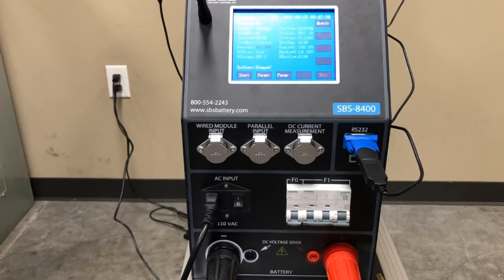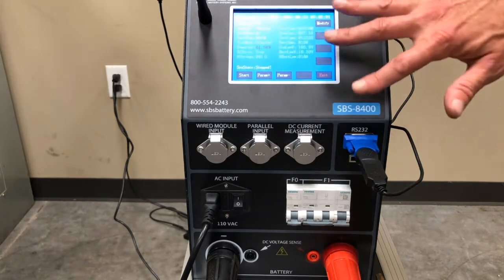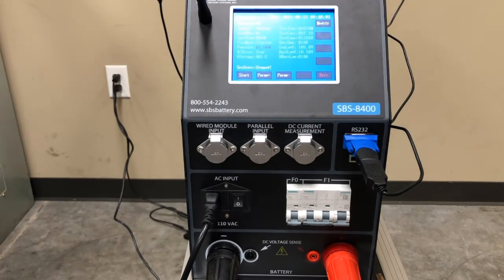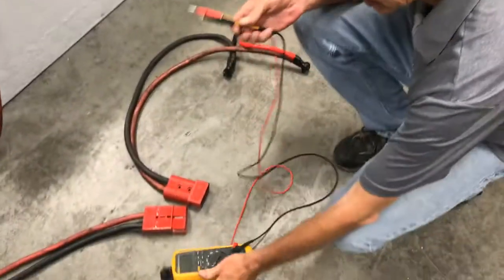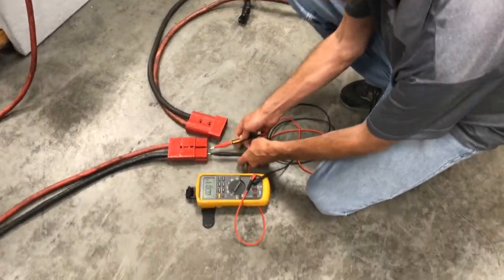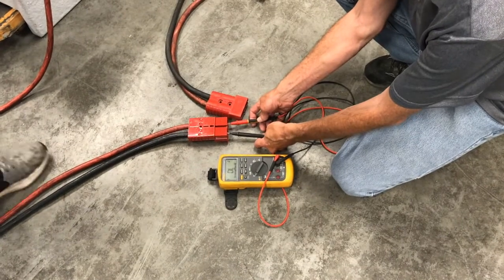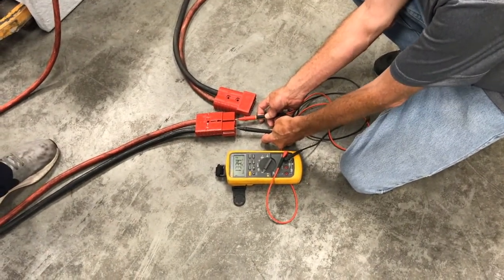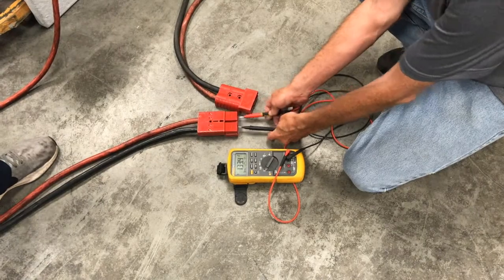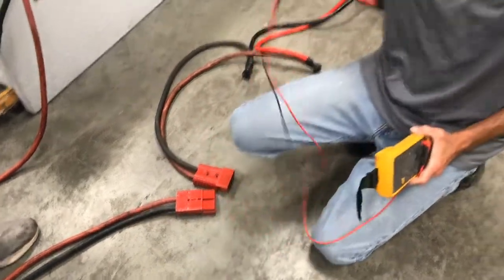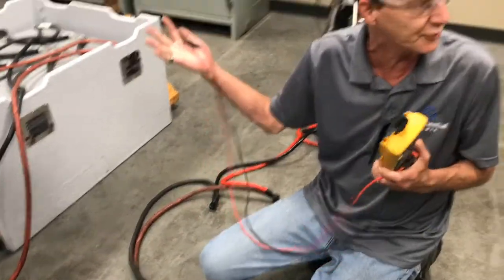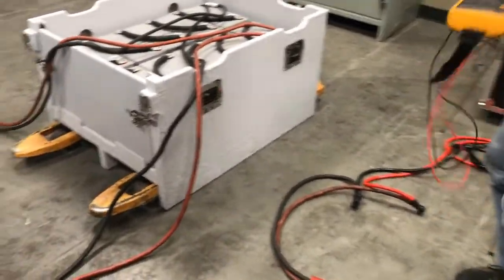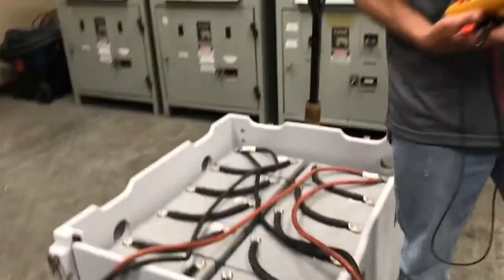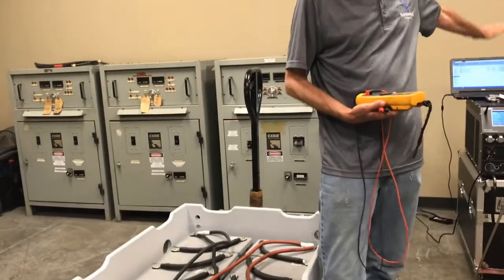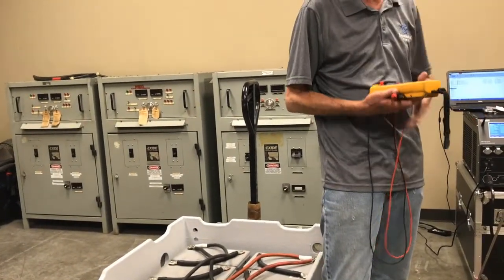So now that I've got the load bank set up and all my parameters programmed, the next thing is to connect the battery to the load bank. I'm going to measure the battery string at the connector that I'm connecting to. Right now I'm at 133.5. I've got 10 blocks, so each block should be at 13.35 roughly, just to give me an idea of where I'm starting. Now if I'm using the wireless modules, they're going to appear on the display and tell me what those voltages are.